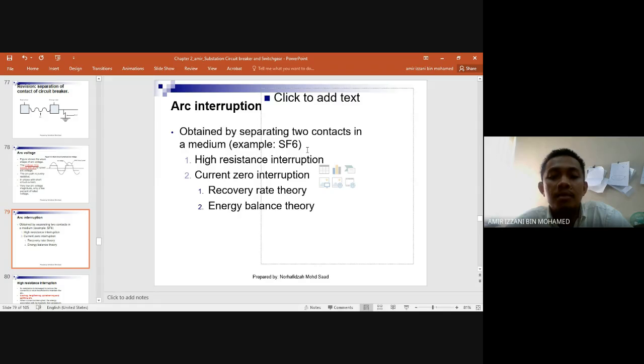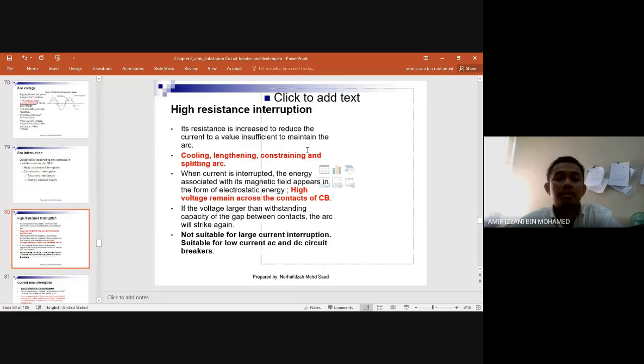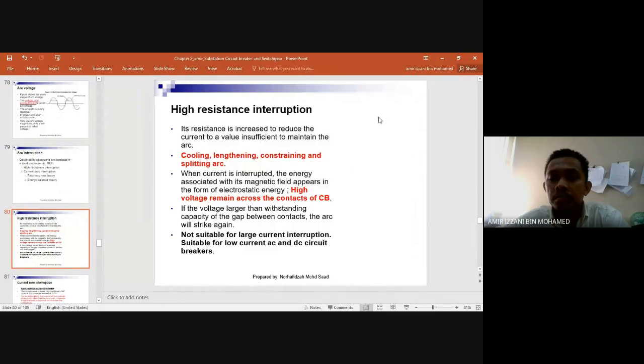Okay, inside current zero interruption, there are two theories that can be used to explain this one: recovery rate theory and energy balance theory. Okay, let's look at high resistance interruption first. The resistance increase refers to the arc, the plasma, to reduce the current to a value insufficient to maintain the arc, by cooling or lengthening, constraining, and splitting the arc. Okay, this is how the resistance is increased.